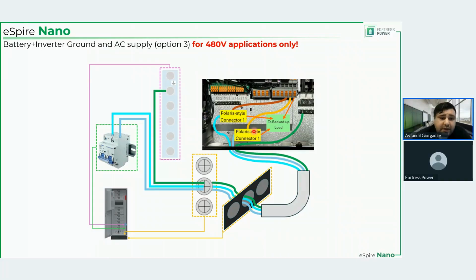One for line 1, one for line 2, or could be line 2 and line 3, or line 1 and line 3. Regardless, you just take one phase, split it, and half of it goes to the backed up panel. By half, I mean half of the conductors connected to them. So if you have a 3-port Polaris connector, one port is occupied by the wire going to the backed up panel, the second one is going to the breaker, the AC supply breaker, and the third one is going to the backed up load. And you introduce something like this, I don't see any trouble with it because that backed up load panel will have the appropriate breaker in it, and you have an overcurrent protection device, this breaker, inside the battery unit.